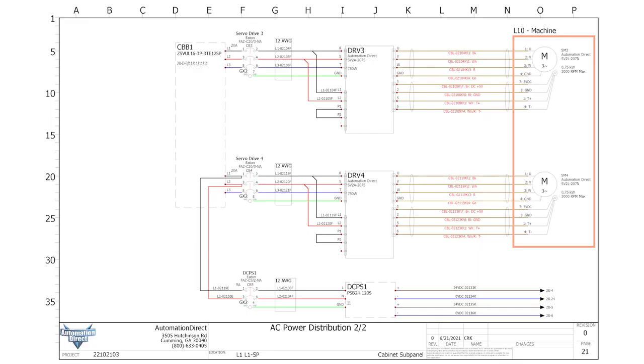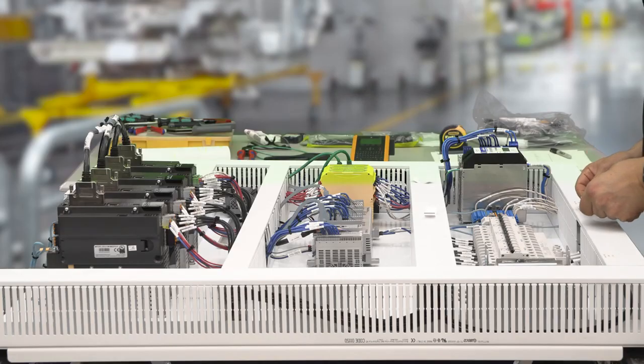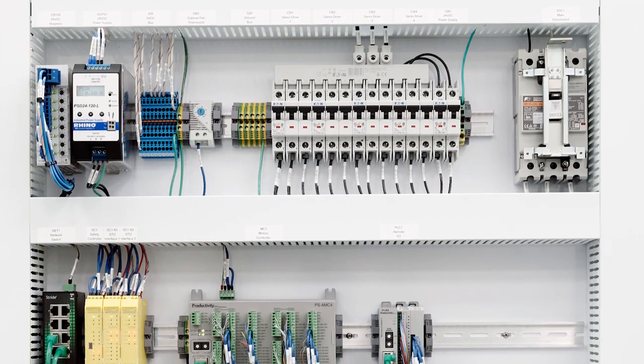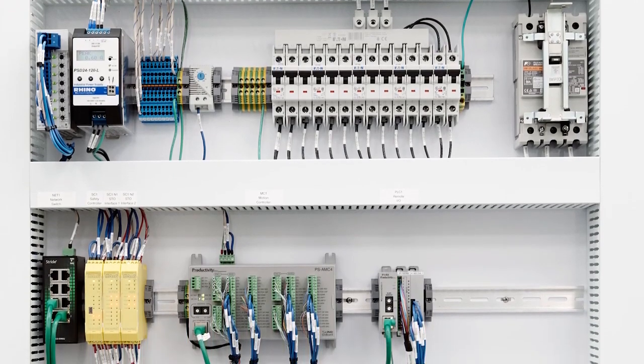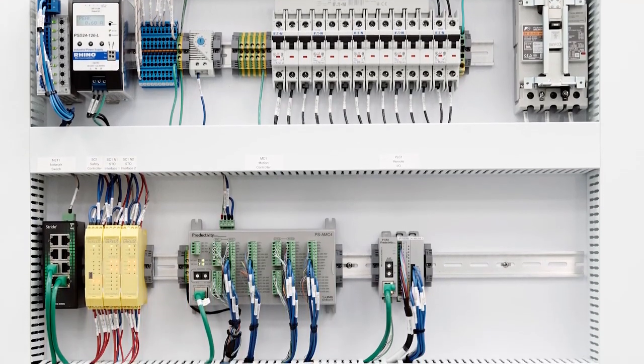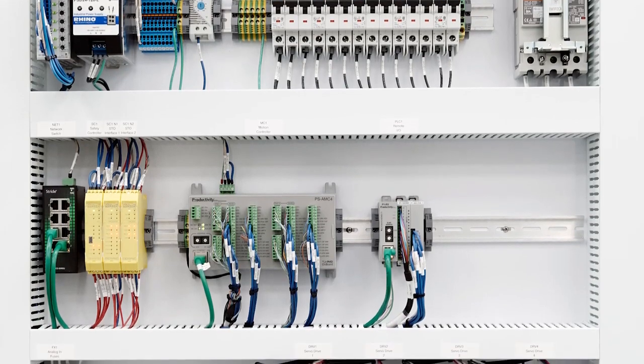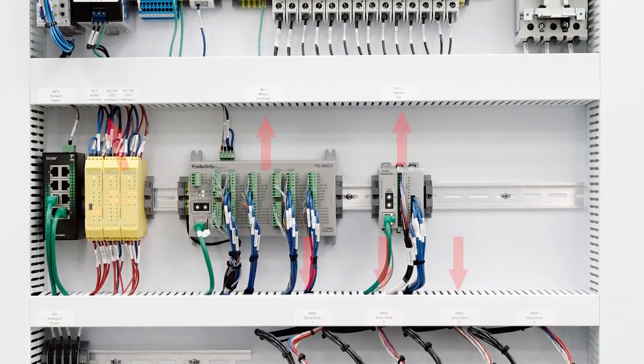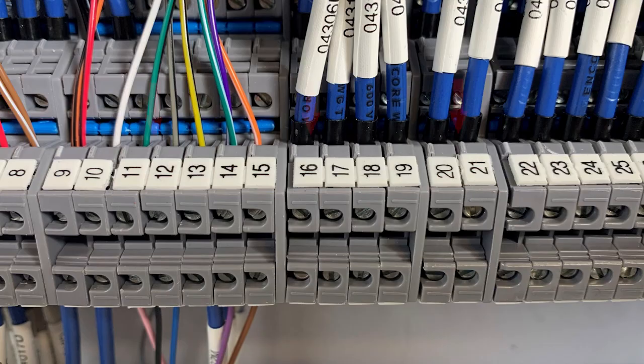Using the schematic package as a reference, apply labels identifying the components and terminal strips. Applying labels on the sub-panel is preferred, but for terminal strips or PLCs with wiring that runs above and below the device, wiring may get in the way of the label. In this case, applying the label to the duct cover is acceptable. Just be aware that years down the road, that cover may go missing. For terminal strips, use marking tags to label each terminal.